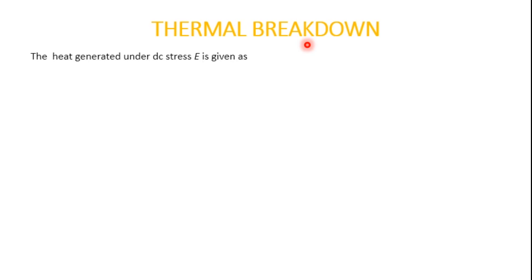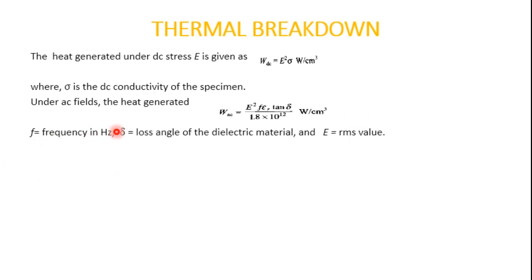The heat generated under DC stress is given by: W_DC = E² · σ (watts per cm³), where σ is the DC conductivity of the specimen. For AC supply, the heat generated is: W_AC = E² · f · ε · tan δ / (1.8 × 10¹²) (watts per cm³), where f is frequency in Hertz, δ is the loss angle of the specimen, and E is the RMS value of the electric field.